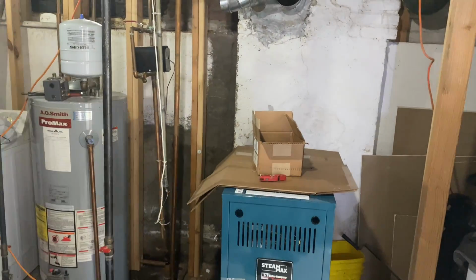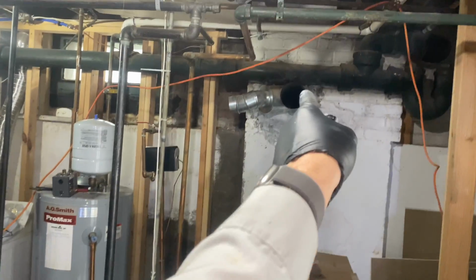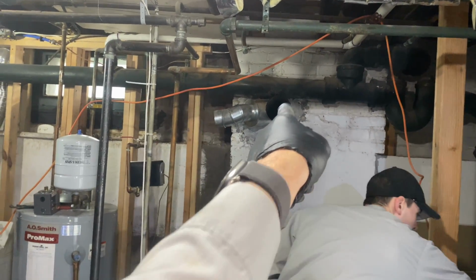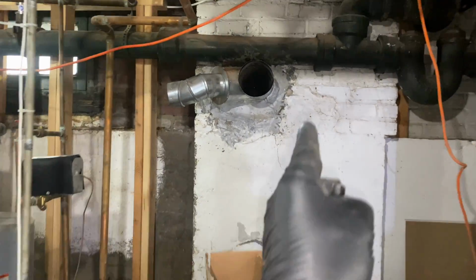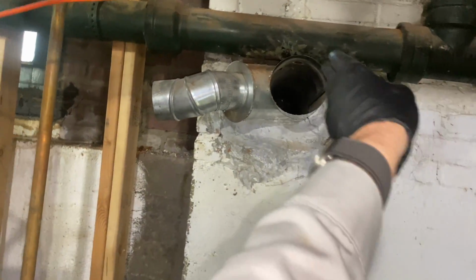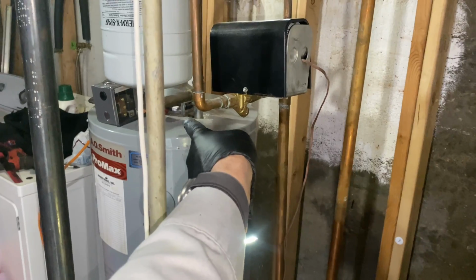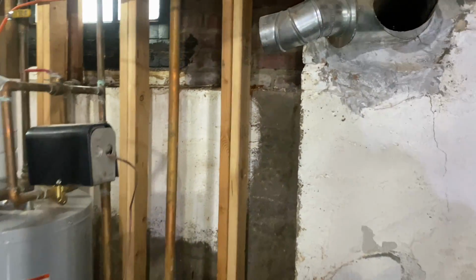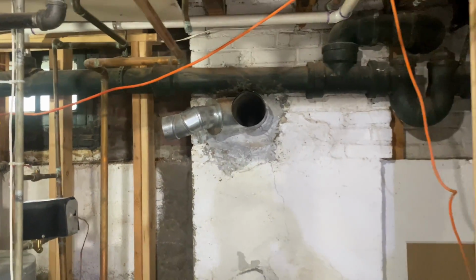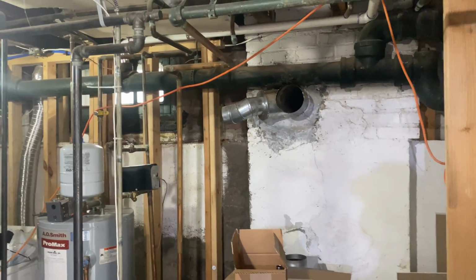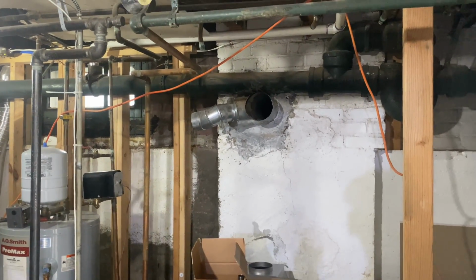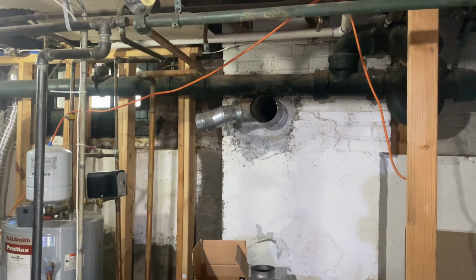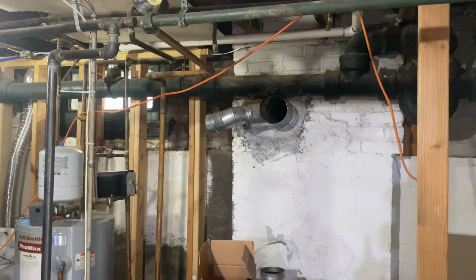Now, that's in a perfect world. Unfortunately, when we have a smoke Y in here, for example, there's a possibility that our exhaust gases will take the path of least resistance, which could go this way and out the diverter on the water heater. So, damned if you do, damned if you don't, but that's why it's always best to hire a licensed professional to not only install your equipment, but also maintain it on an annual periodic schedule.